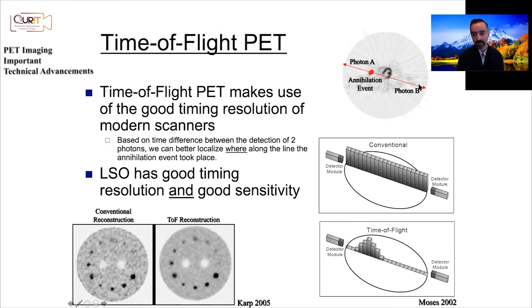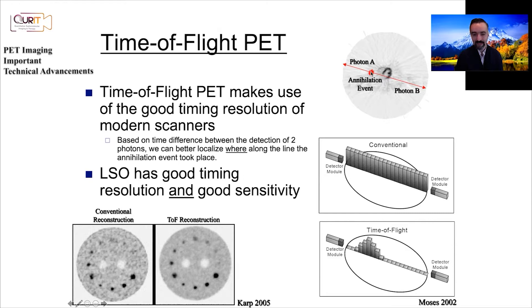What does time-of-flight mean? If the source of an event is not exactly at the center of the field of view, photon A reaches one detector a bit faster than photon B reaches the other. If you have really good timing resolution, you can use that timing information to narrow down the origin — not from somewhere along the entire line of response, but to a smaller area around the most likely position.